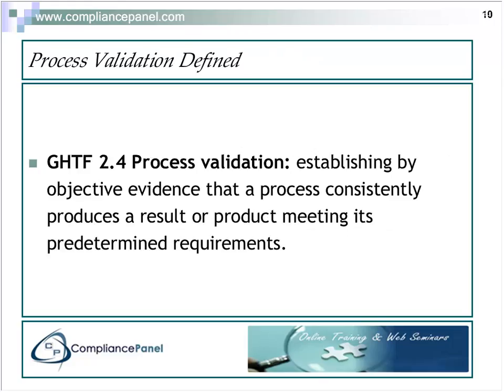So as we start digging through these documents now in the GHTF, and since this is the main document which is applicable to the medical devices, we will spend the majority of our time on this document. There is a definition that tells us that when we do process validation, what we're trying to do is establish by objective evidence that a process consistently produces a result or a product meeting its predetermined requirements. So the objective evidence means we must have some documentation. That is the evidence that the FDA certainly is looking for.